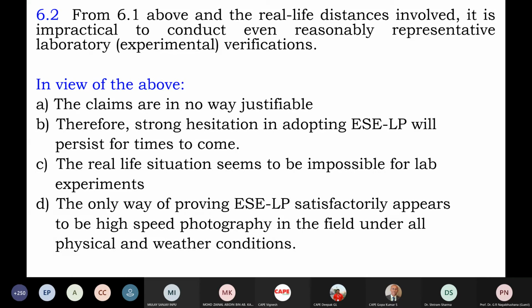So in view of the above — and these are only a few, there can be much more — for example, when the electric field intensities are compared between the rod-plane gap and rod gap, the electric field intensity at the tip of the rod, ESE or Franklin rod, will be much higher. When the field is much higher, the time lapse may become much less. These time-lag characteristics, as we call them in high voltage laboratory experiments, are studied very commonly in all good ME high voltage courses. If the electric field strengths are much higher, it's likely that the time lag of 10 microseconds may become very small, of course subject to other parameters like polarity, the presence of dust, etc.